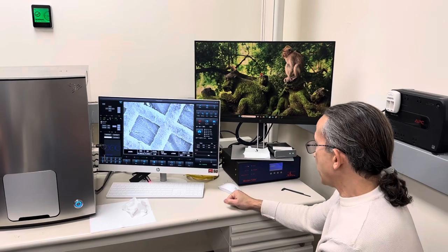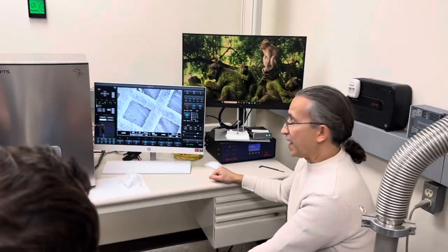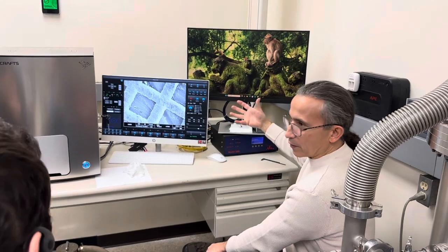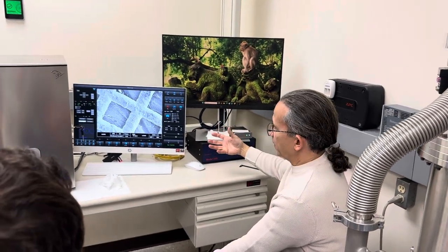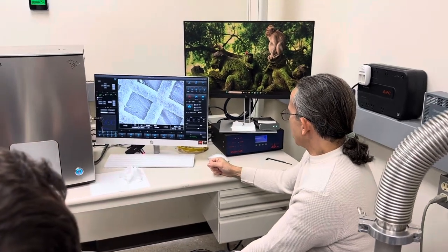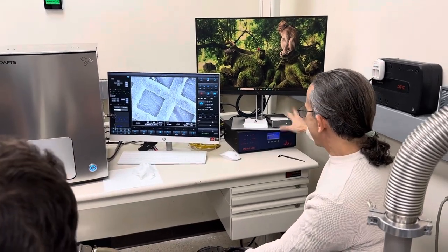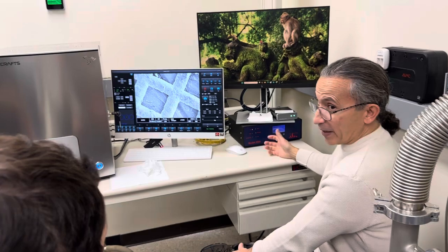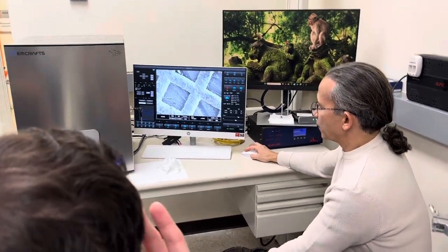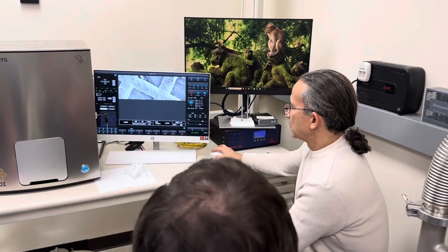The rate and the preamp are blinking green. So what that means is that we're actually seeing information. Even though I don't have my software window open, I'm not looking at anything, as long as I have a beam, and as long as my detector is on, then it's picking up X-ray events.